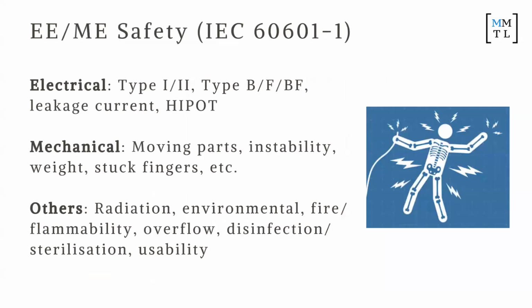Okay. Now, the next standard that you need to adhere to, and some of this is less appropriate if you're just doing 3D printing, but it's more appropriate if you're doing an actual medical device, is you need to demonstrate electrical safety. Okay, that just means that you're not going to kill the patient accidentally with a voltage spike or a giant shock or something that actually leads to damage, right? You need to demonstrate mechanical safety.